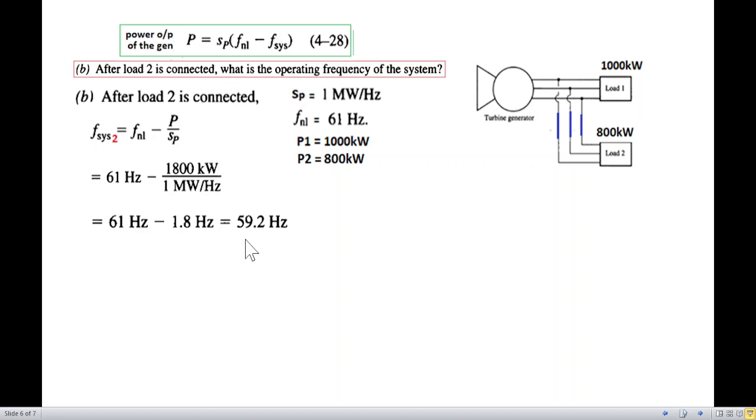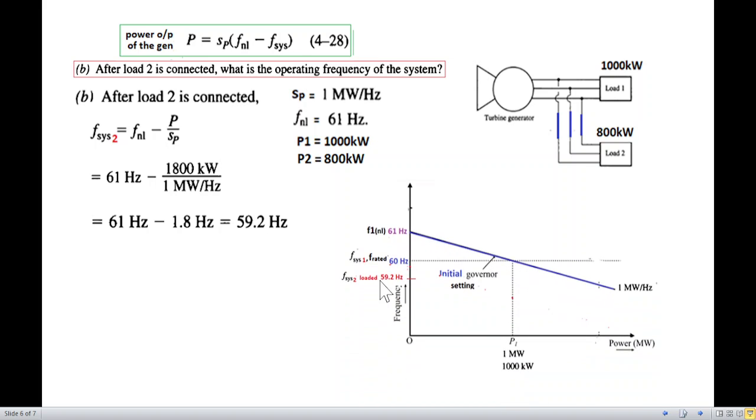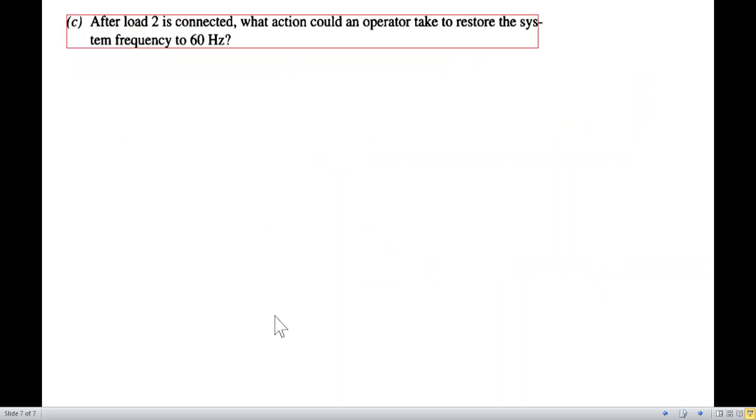And this drop is not acceptable. It should be very near to 60, about one or two percent variation is acceptable. So we have to do some things to adjust this frequency. Now let's see how it looks in the graph. We were up to this point. Now the new frequency, because of the added load, has come down. It is now at 59.2. So it has dropped by 0.8 Hz.